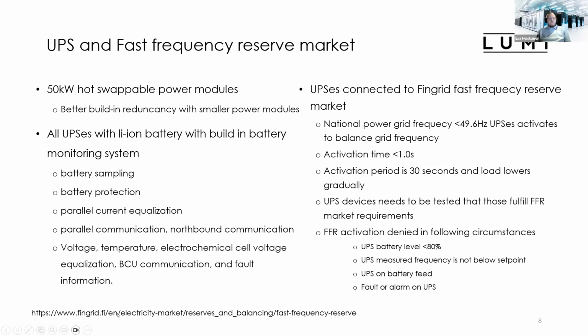There is more information about this market on the Fingrid side, where you can check in more detail what this market is about. This differs a little from the traditional reserve market, where you have a big UPS system balancing the demand on the grid. When the power consumption in the grid increases over the production, these kinds of devices can start to balance the demand on the grid. So this is a slightly different mechanism, and it is pretty new in the Nordics too.